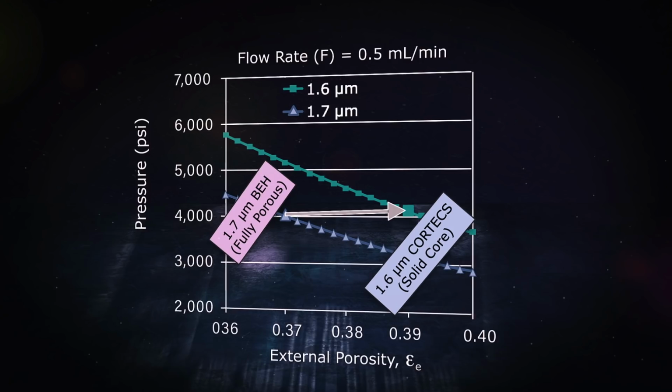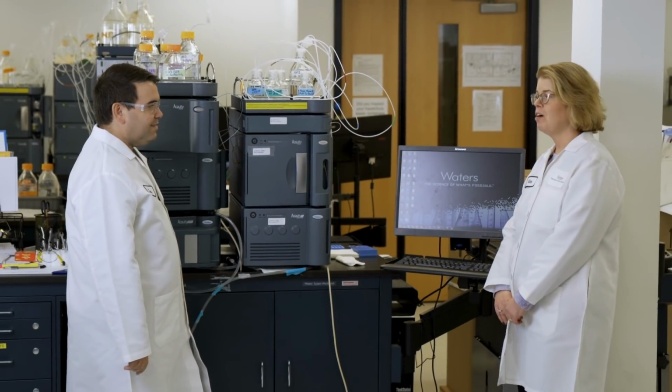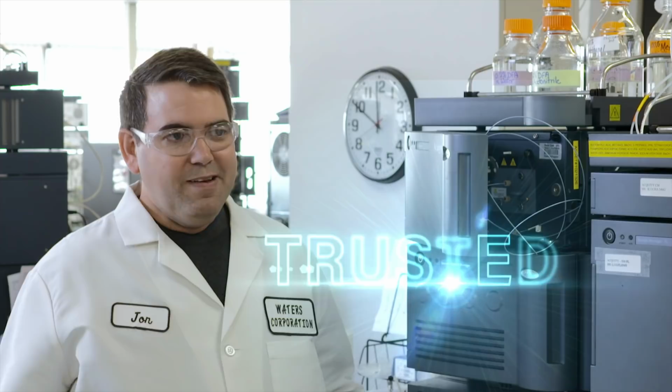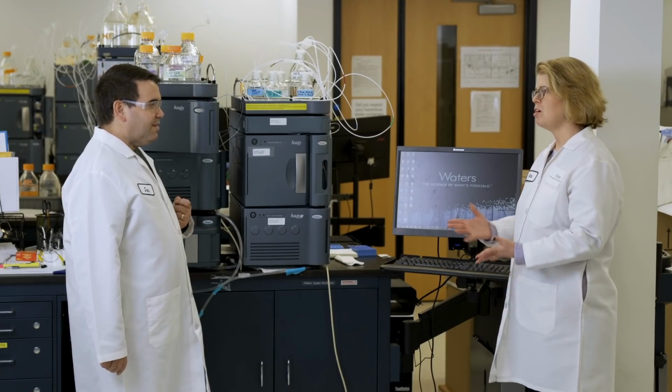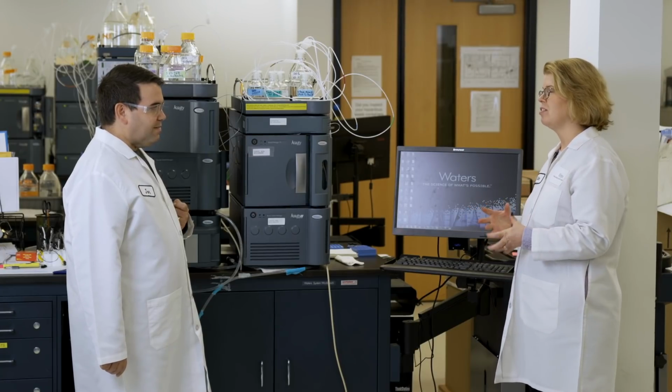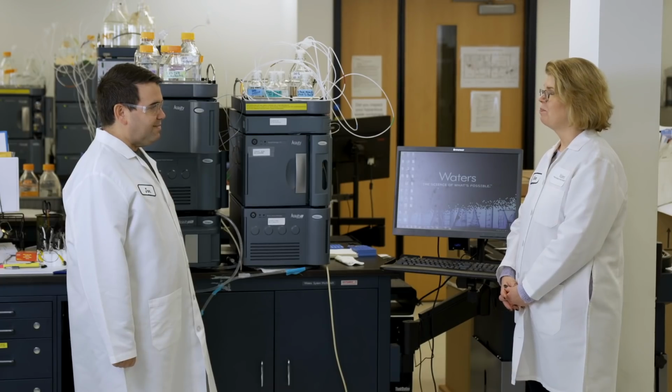Oh, very interesting. So JT, how do you want to call this myth? Yeah, it's trusted. Solid core particles do provide lower back pressure when compared to fully porous particles, especially if they're of equivalent particle size. Yep, so we should also mention, though, it really has nothing to do with the particle itself. It's more about, as we saw, how efficiently it's packed in to create a stable bed within the column. Exactly right. Solid core columns you can pack at a little bit of a higher external porosity, and that's beneficial when it comes to pressure. Absolutely. So let's write this up.